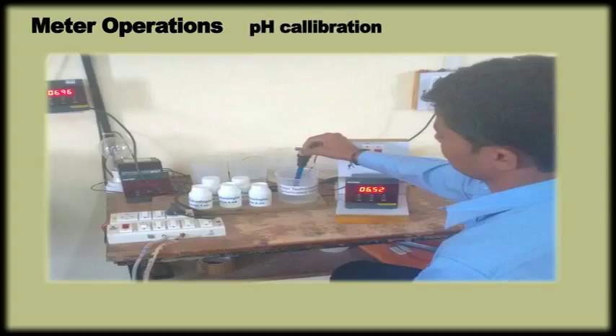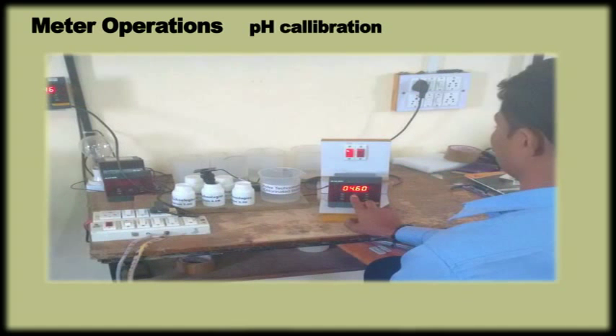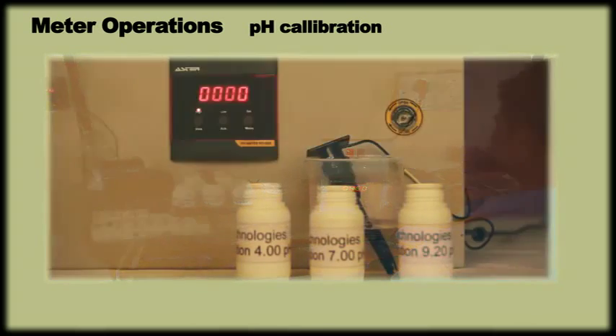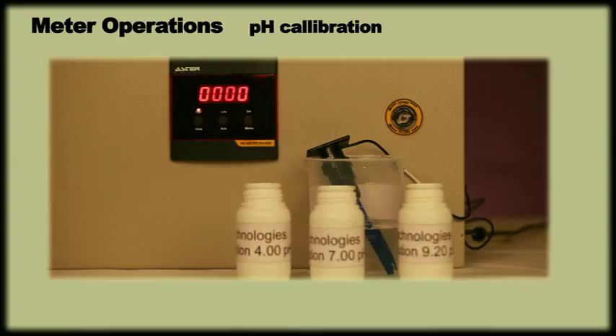On-site calibration. The pH meter supplied comes duly calibrated by experienced professionals from our factory. In case the need arises for on-site calibration, let us learn the procedure. To start the calibration procedure, please ensure the availability of fresh buffer solutions of 7 and 4 or 9.2 pH.